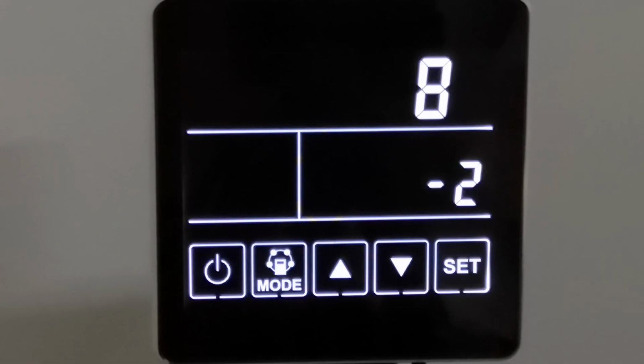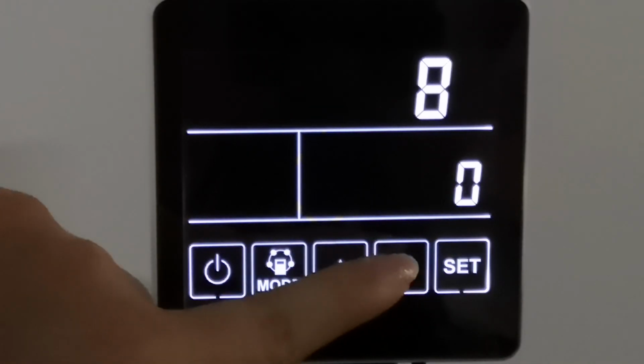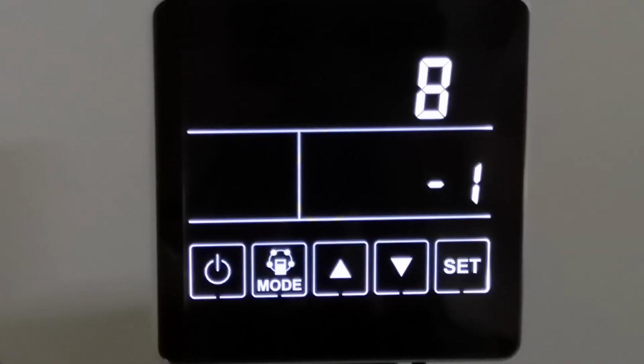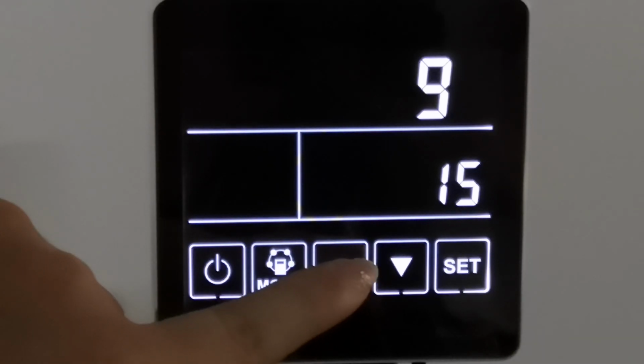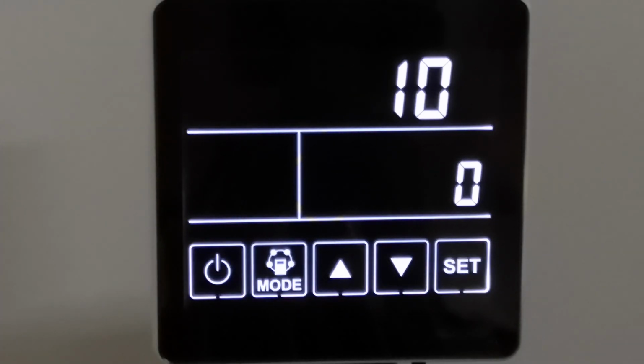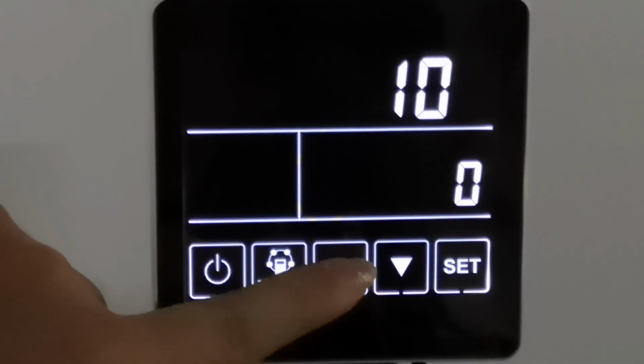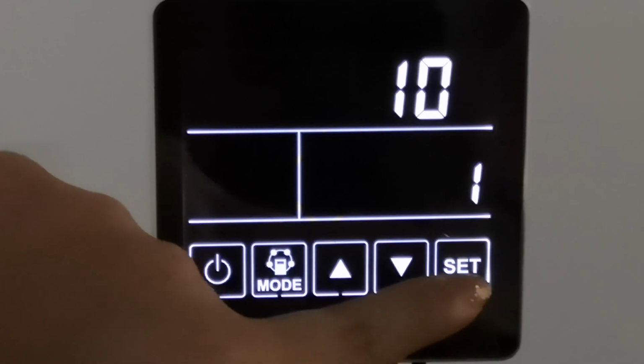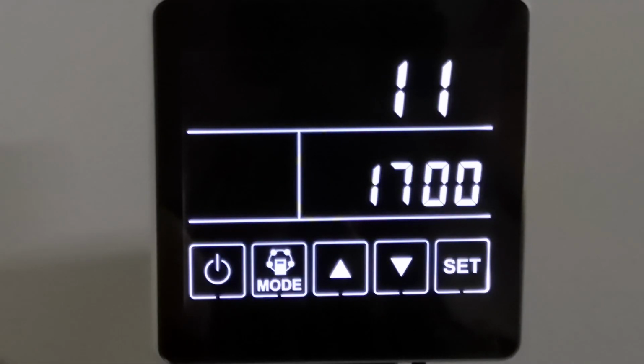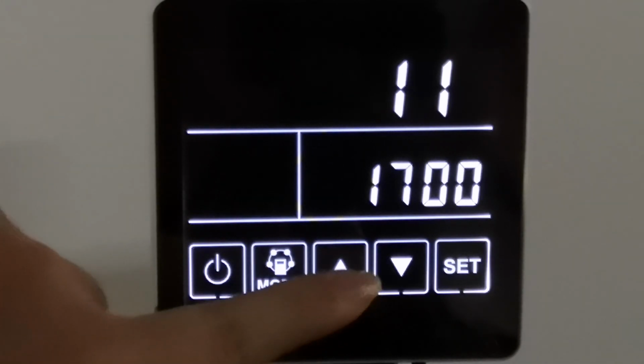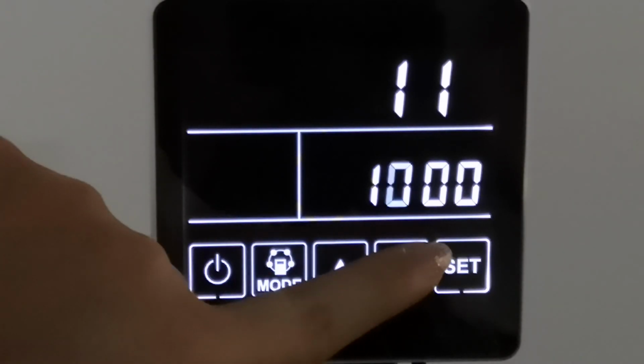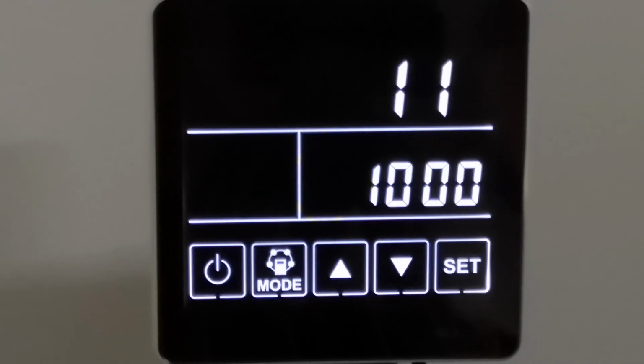Parameter 8 refers to the defrost entering temperature. Once the temperature drops to -1 degree and lasts over 1 minute, the defrosting function will start operating automatically. Parameter 9 refers to the defrosting duration time, that is, the running time of the defrosting. Parameter 10 refers to whether the CO2 display function is valid or not. Value 0 means invalid, and value 1 means valid. Parameter 11 refers to the CO2 concentration setting. If the CO2 sensor detects that the CO2 concentration is higher than the setting value for more than 5 seconds, the ventilator will start up automatically and run at high speed. Only when the CO2 concentration is lower than the setting value for more than 5 seconds will the ventilator return to the previous condition.